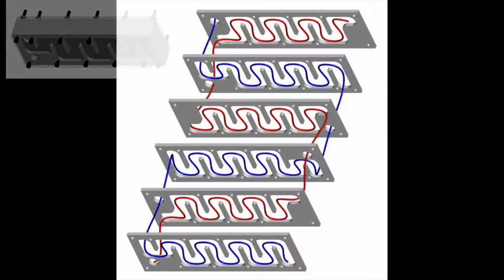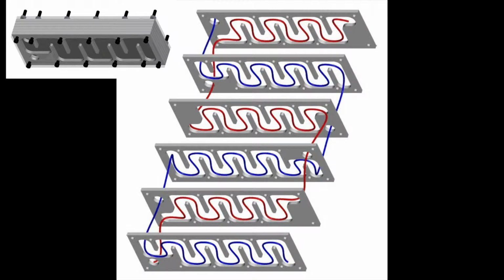Here is a diagram of how the hot and cold water flow within the heat exchanger. The hot and cold water inflows are on opposite sides from each other. Water flows diagonally up or down within each layer. The gaskets direct the flow and allow the other temperature water to pass through that layer.